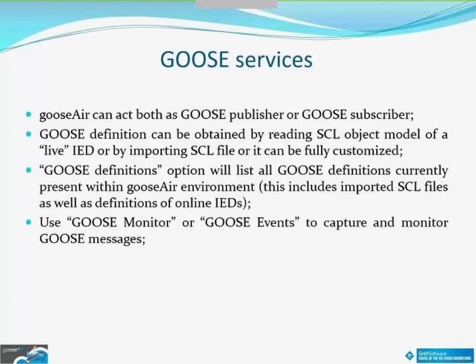The GOOSE monitor tool presents every single captured GOOSE message, regardless of the trigger that has occurred. While a GOOSE event monitor is more like an event-based monitor, meaning that only GOOSE messages which are triggered by a new event shall be presented, which can be very suitable for monitoring networks with large amounts of GOOSE traffic.